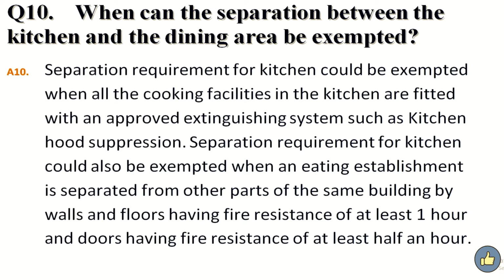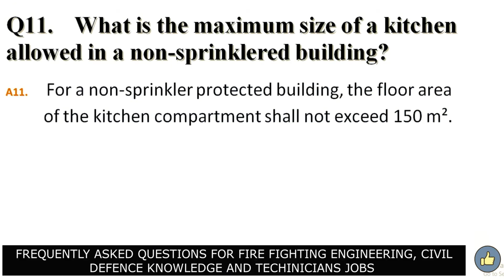Answer. Separation requirement for kitchen could be exempted when all the cooking facilities in the kitchen are fitted with an approved extinguishing system such as kitchen hood suppression. Separation requirement for kitchen could be exempted when an eating establishment is separated from other parts of the same building by walls and floors having fire resistance of at least 1 hour and doors having fire resistance of at least half an hour. What is the maximum size of a kitchen allowed in a non-sprinklered building?